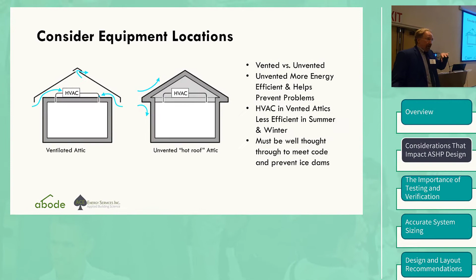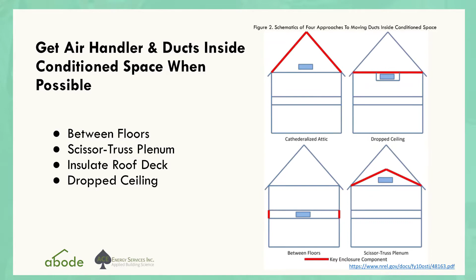This slide is conceptual. You can put an air source heat pump system, or the indoor air handler, in a few places. The upper left is a cathedralized ceiling, that's your insulated roof deck. The one on the right is dropping it below a cold attic, making a soffit down there for the heat pump system. The lower left is sandwiching it between floors, which is great because then it's inside conditioned space. On the right, you can construct, in this case, a scissor truss plenum that brings the equipment into a conditioned space built inside the attic.